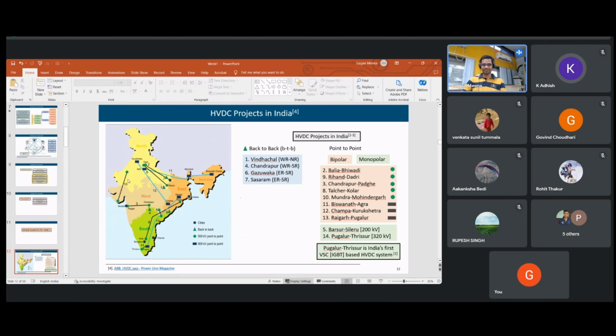We can see all these on the map. For point to point lines, there are two separate dots, and between them there is a connection by a transmission line. But for back to back, you will see only four stars. That means there is a connection, but it is very small, because in these back to back converters the inverter and converter are both placed in the same substation, connected by only a sufficiently small line. But in point to point, the converter is at one place and the inverter is at the other place, on the other side. So that is the main difference.